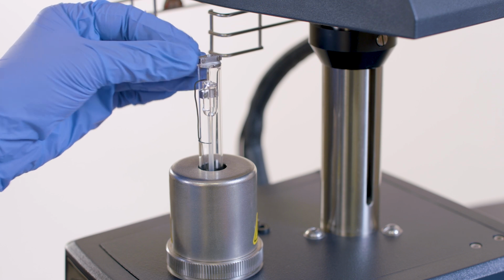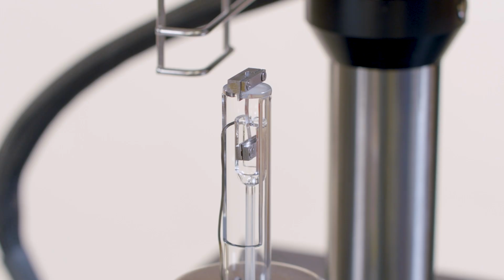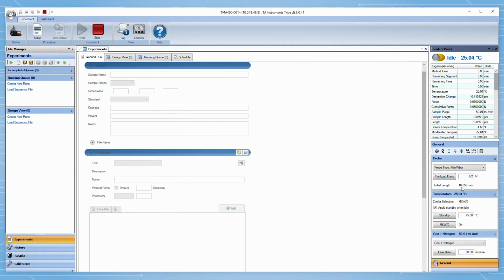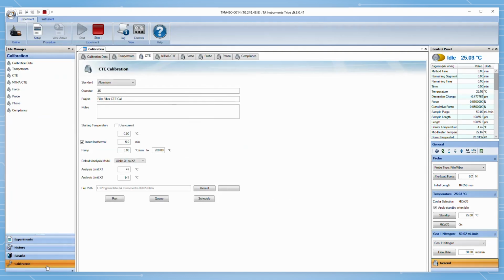Verify the alignment. After loading the sample, check that the clamp is properly seated within the probe and stage. Look at the measured length. Using the sample block, samples should measure around 8, 16, or 24 millimeters. Typically, a ramp rate of 5 C per minute is utilized over the region of interest to generate the calibration constant. In this Tech Tip, we have covered how to calibrate the film fiber probe on the TMA 450.